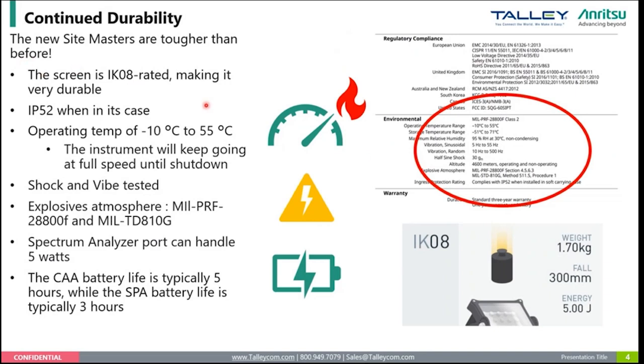The screen itself is IK08 rated, and this is applied to all of our newer instruments in the same design, a new platform that we're launching. What does IK08 rated mean? You can see this image here. It's essentially a rating. There's IK07, IK09, but essentially they describe how much force the screen can take before it breaks, and they test it by dropping a set steel ball bearing from a set height. In this case, they dropped a 1.7 kilogram ball bearing at 300 millimeters, and the screen did not break. In other words, in most cases, I feel like the instrument inside will break before the screen breaks. That's how tough the screen is.